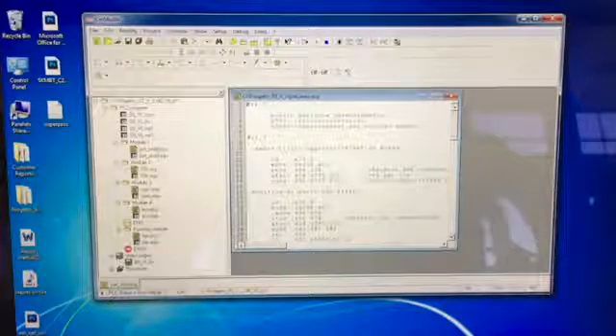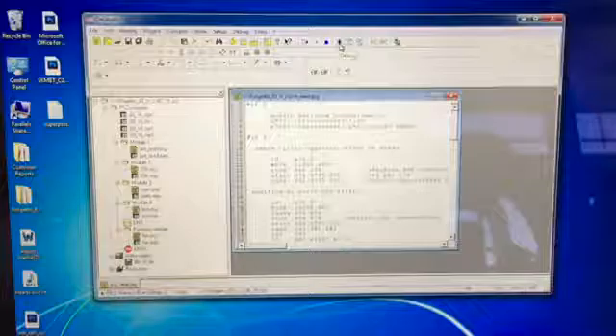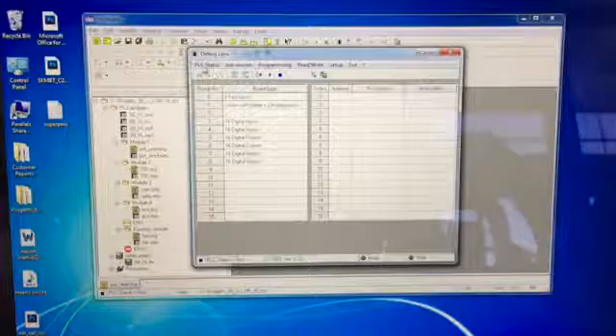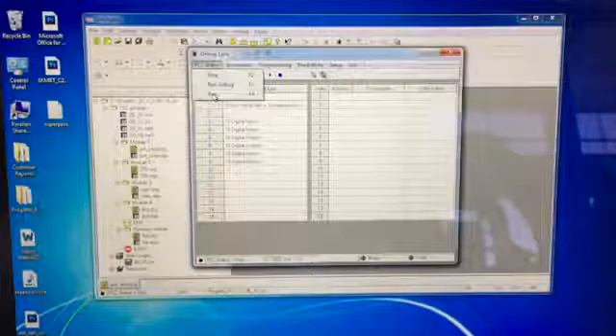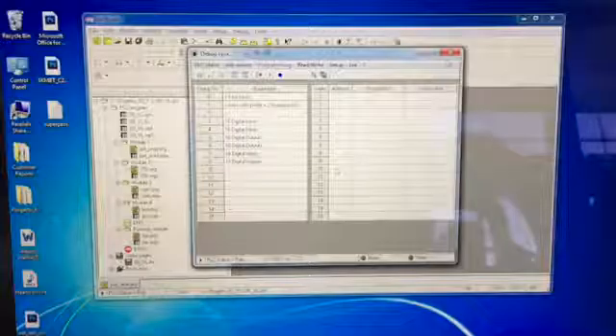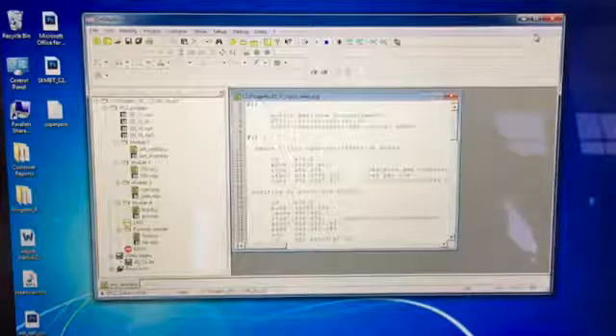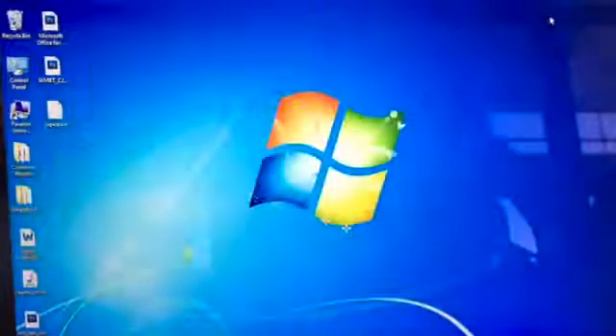You can look down here in the lower left. It says PLC status run debug. So we've got to open the debug which you can do from the toolbar menu at the top here. We're going to go to PLC status and we're going to choose run. You can see down to the lower left that PLC status is now changed to run. We click OK or close that window. Our control is ready to go. We can go ahead and close the program.